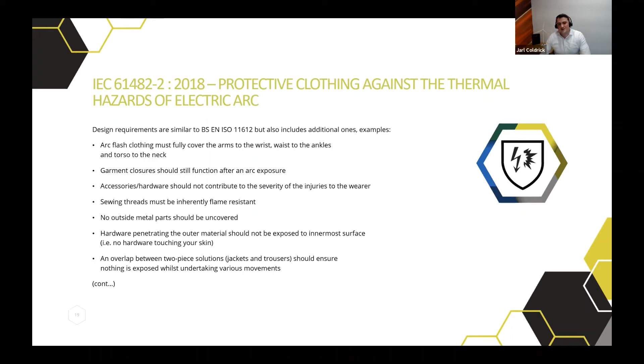In terms of arc flash testing, it's essential that both the fabrics and the garment are tested, not just the fabrics. The other factor is distance: the actual amount of incident energy varies depending on how far you're stood away from an arc flash exposure. Being a foot away compared to a meter away makes a massive difference when there's a risk of arc flash.